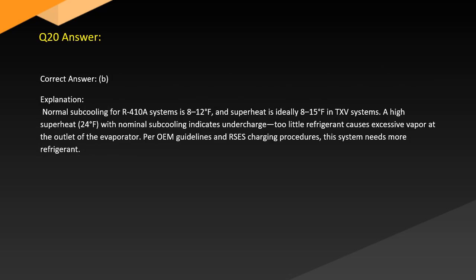Answer. Correct answer. B. Explanation. Normal subcooling for R-410A systems is 8 to 12 degrees, and superheat is ideally 8 to 15 degrees in TXV systems. High superheat of 24 degrees with nominal subcooling indicates undercharge. Too little refrigerant causes excessive vapor at the outlet of the evaporator. Per OEM guidelines and RSES charging procedures, this system needs more refrigerant.